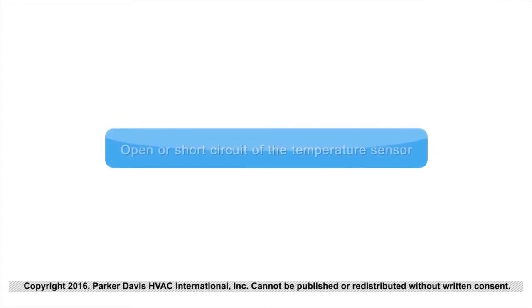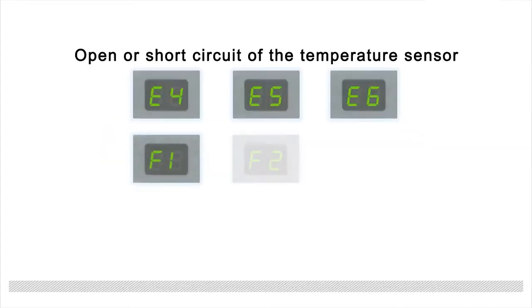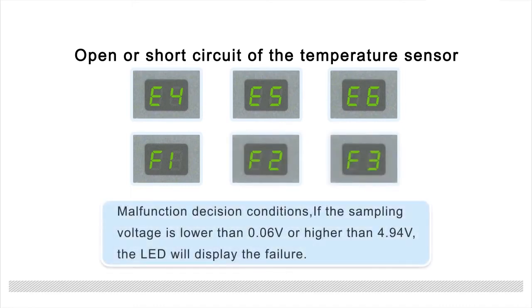When indoor unit displays E4, E5, E6, F1, F2, F3, those indicate open or short circuit of the temperature sensor.